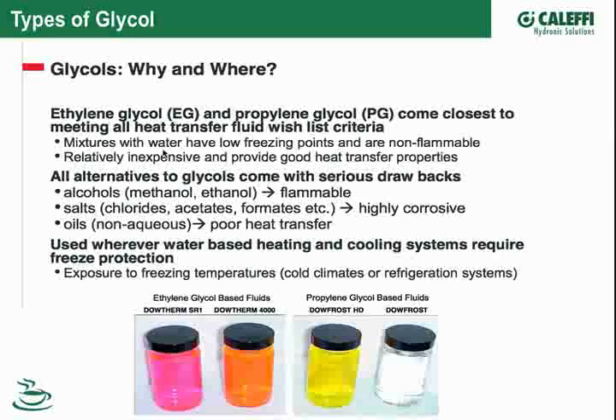In general, ethylene glycol will be a little more forgiving than propylene glycol from a materials compatibility perspective. But are there limitations? Yes. With things like PVC and CPVC, you need to check with your pipe manufacturer for their recommendation, because some say don't use our PVC or CPVC products with any glycol at all. Others say you can use them but don't exceed certain concentrations, whether it's 25%, 30%, or whatever. And others say they have no issues at all.